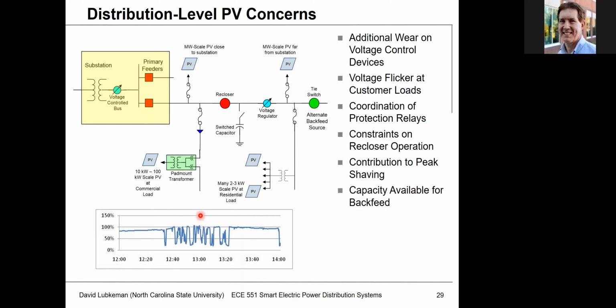The issue we run into, especially with PV, is a lot of these resources are dependent on the irradiance of the sun. So if we have clouds, this impacts the irradiance and this impacts the power output. The power output from each of these individual units modulates up and down, maybe between 100 and 30%. As the power modulates, it causes fluctuations in flow back and forth on this grid that cause rapid fluctuations in voltage. It can confuse our relaying, put constraints on how we operate our protection, and causes a number of different problems.